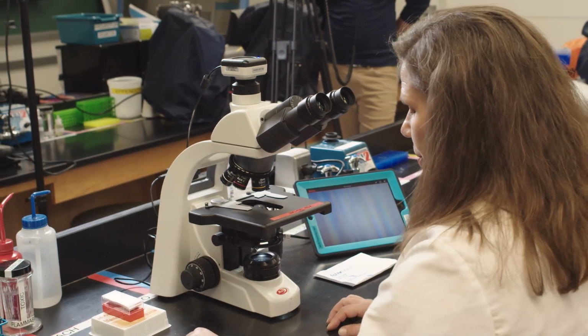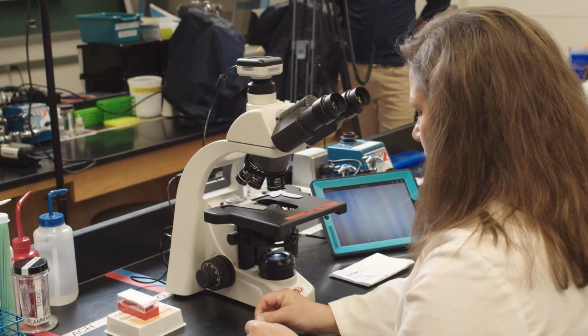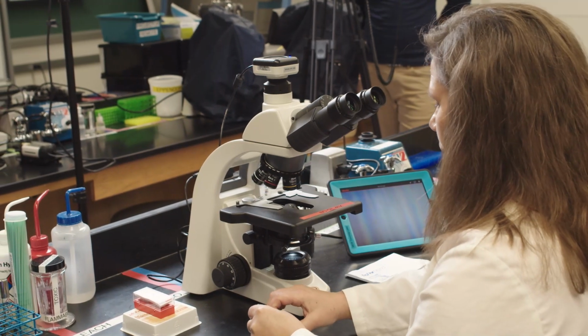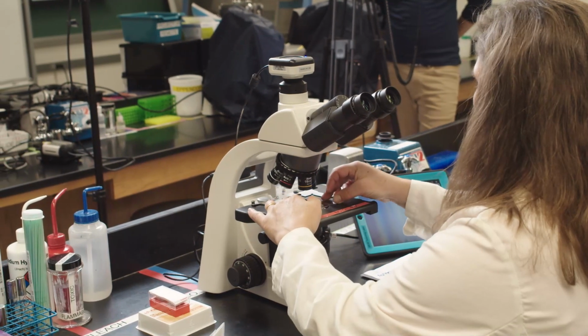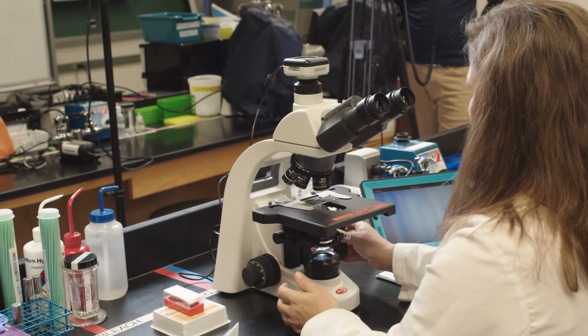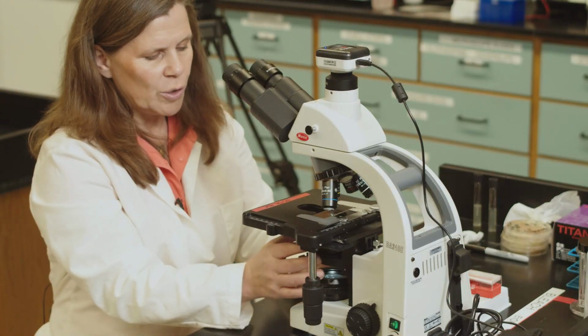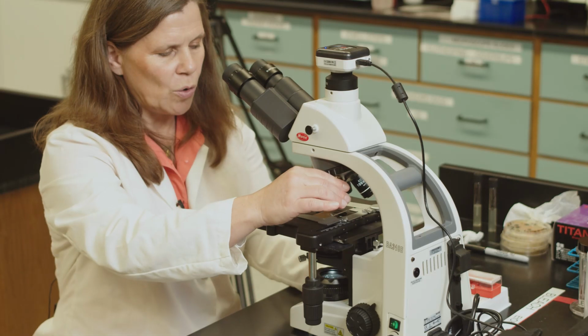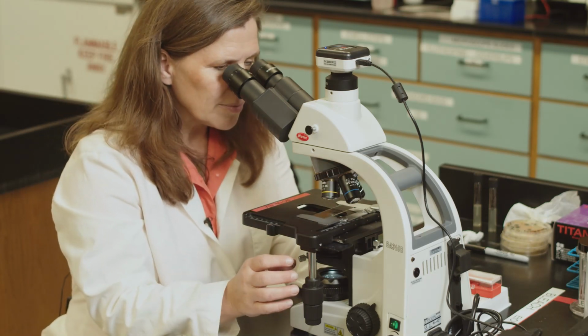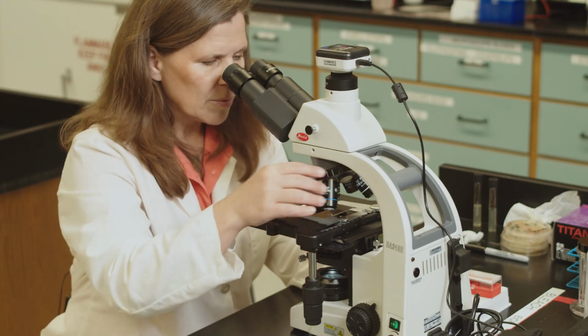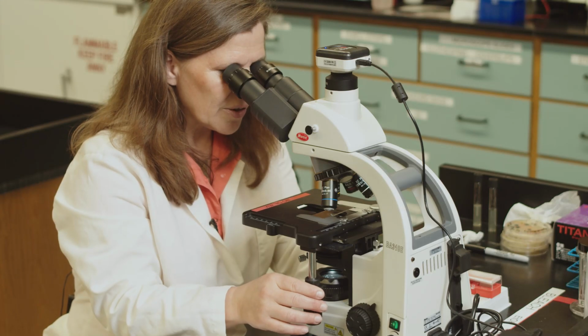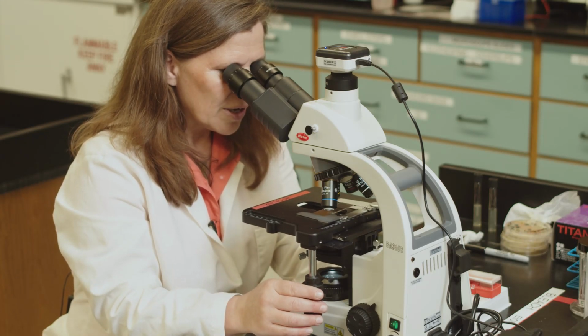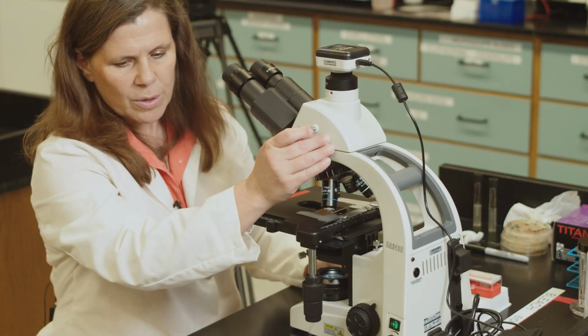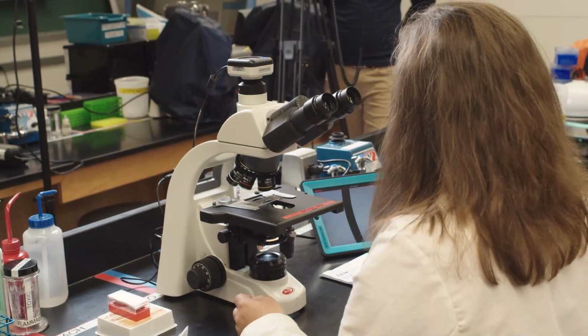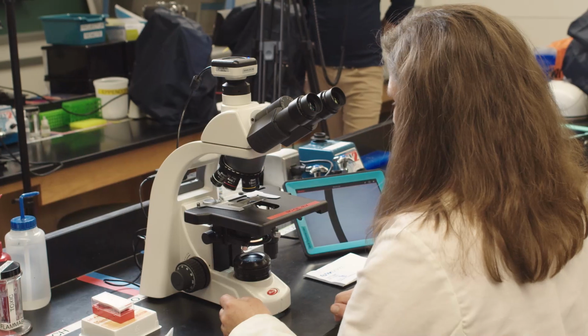So in order to do Köhler illumination, you put your mounting slide or any other slide with something on it. You have to first focus on something on the slide. If it's too bright, you can close it. You can do this at 4x or at 10x. And this indicates you have the correct focus and adjustment of your microscope. So you focus on something on the microscope. You can see that on the monitor.